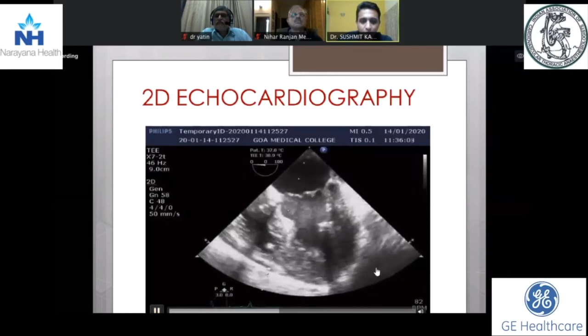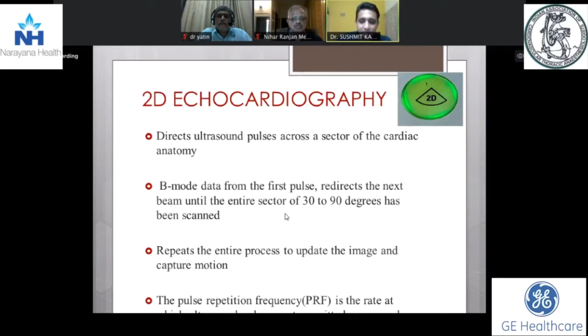So this is a sector of a 2D echocardiography mode, which we use most commonly. In 2D echo, we direct the pulse across a 30 to 90 degree sector of cardiac anatomy, and we repeat the entire process to update the image and capture motion. There are certain terms which we should know when we are discussing 2D echo. One is the pulse repetition frequency, which is the rate at which ultrasound pulses are transmitted per second. Next is the frame: each image which is created by a sector is known as a frame, and the number of frames in a second is known as frame rate.